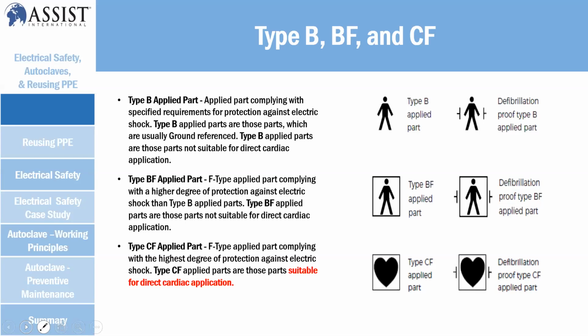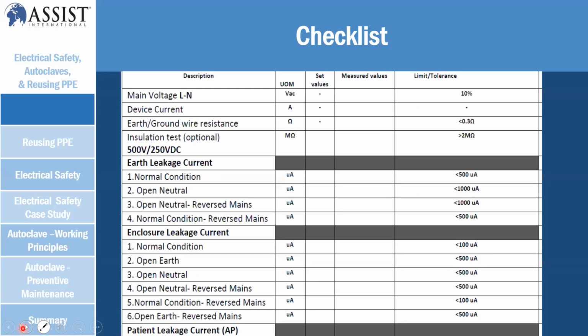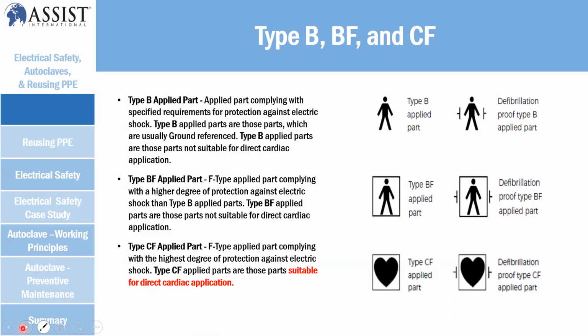Defib proof means that when you're applying, for example, ECG on a patient, and that patient needs to be defibrillated, you can defibrillate the patient without removing the ECG cable. That's the reason they mention defib proof type BF. Okay, and the type CF applied part is normally for cardiac use. So you can see type CF and type CF with defib proof as well.